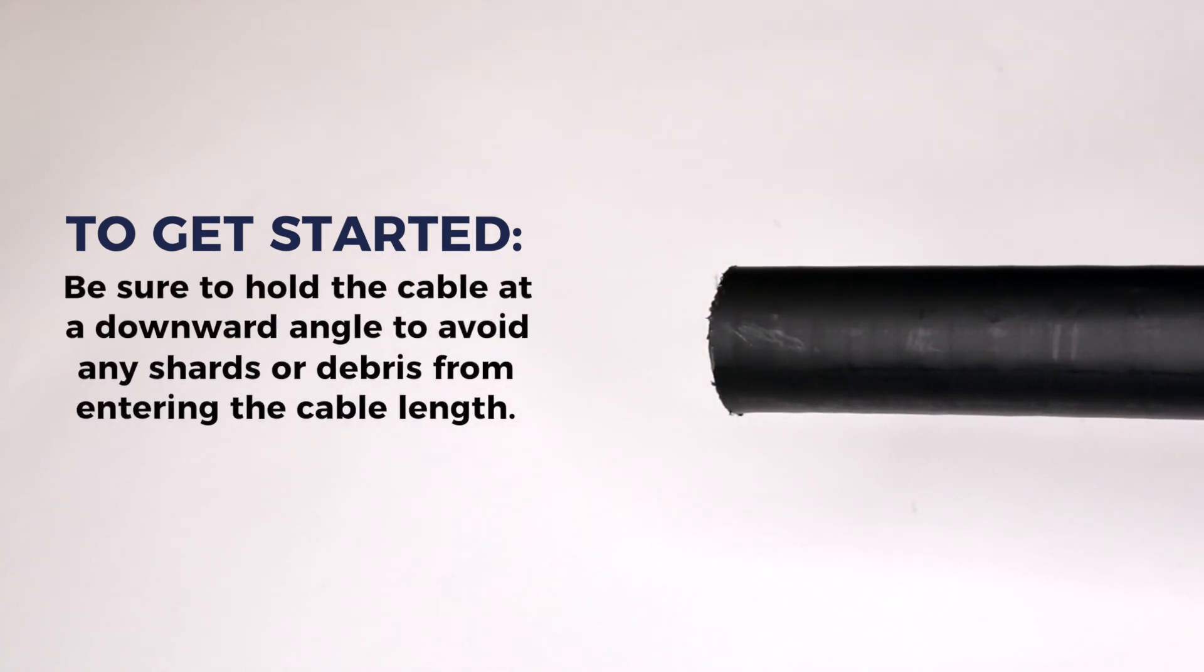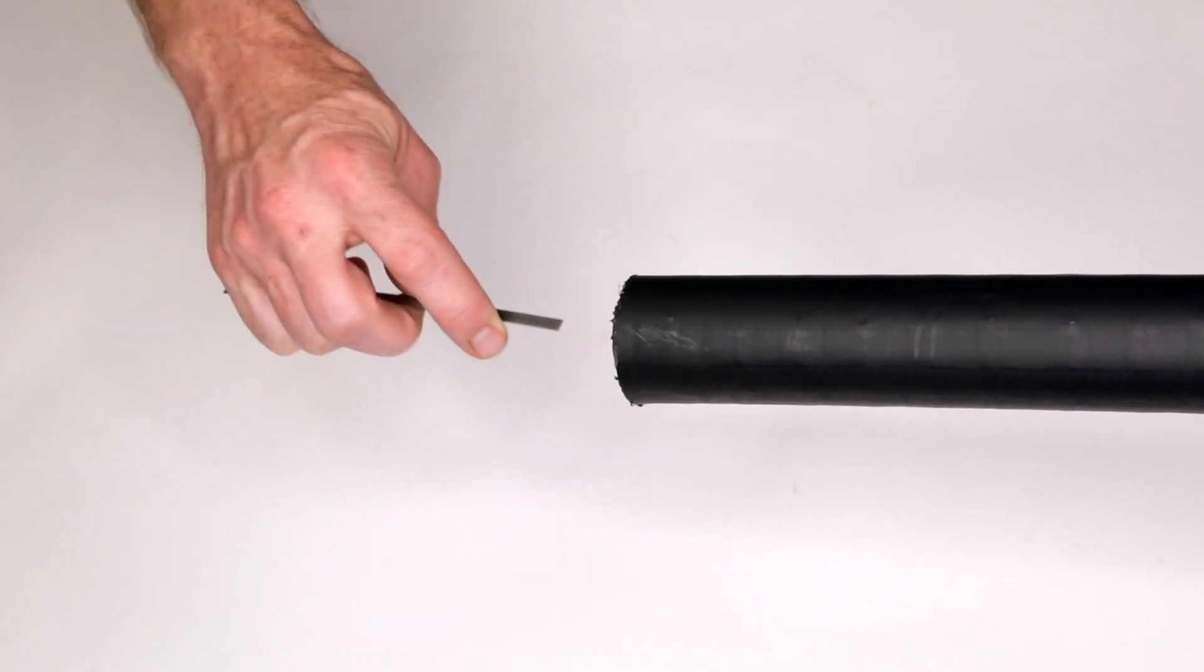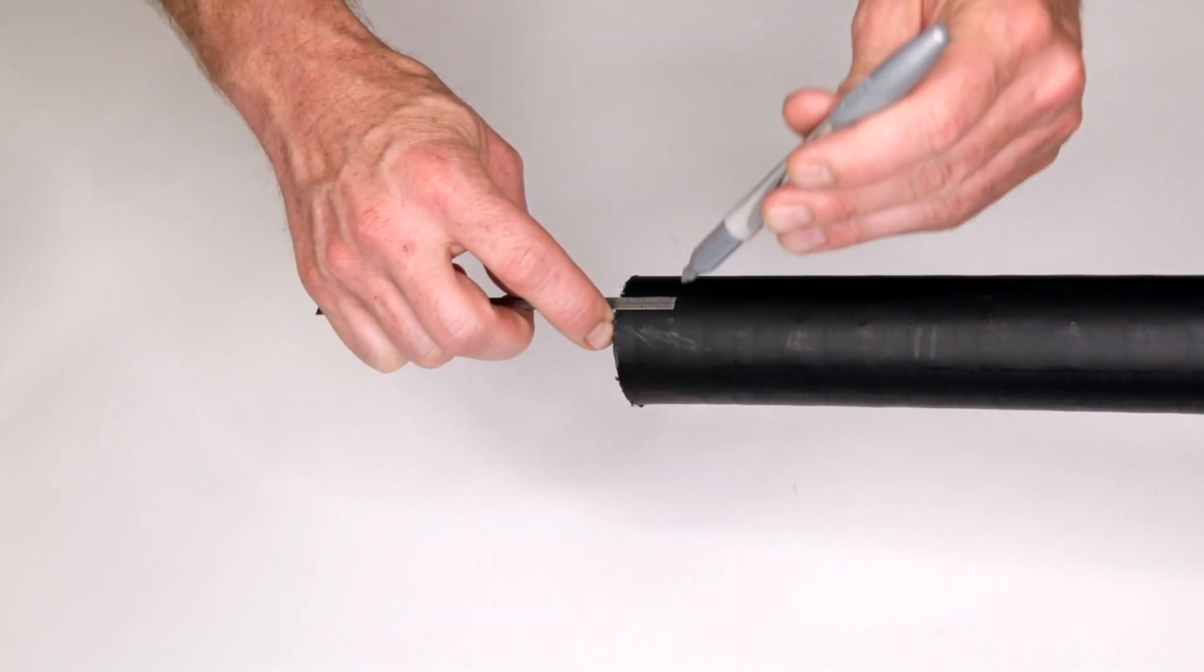Hold the cable at a downward angle throughout the entire process to avoid any shards or debris from entering the cable length. Locate the first dielectric disc by inserting a small ruler or wire into the cable end and mark the location on the jacket surface.